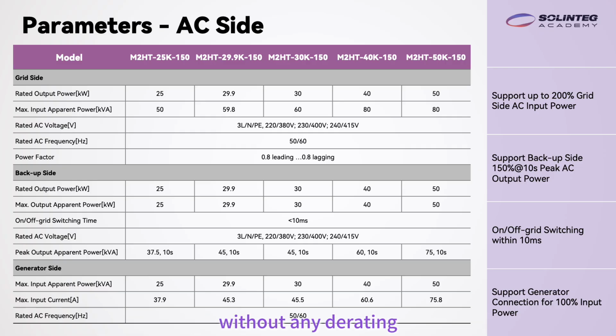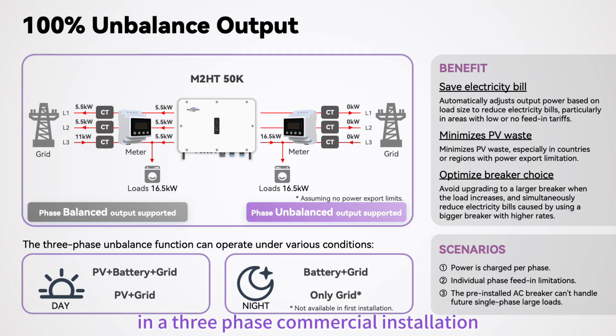without any derating. In a 3-phase commercial installation, load distribution across the 3 phases is rarely perfectly balanced. The M2HT addresses this with full 100% unbalanced output support, meaning it can dynamically adjust its output on each phase independently, rather than being constrained to balanced 3-phase delivery. This is particularly useful in 3 scenarios.